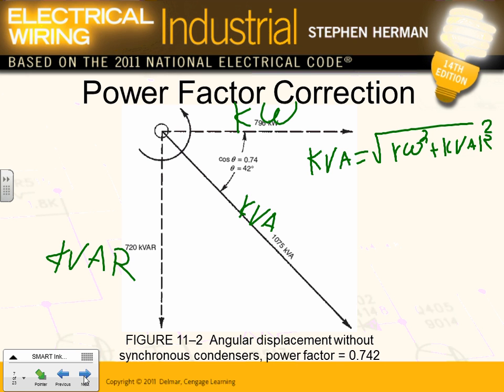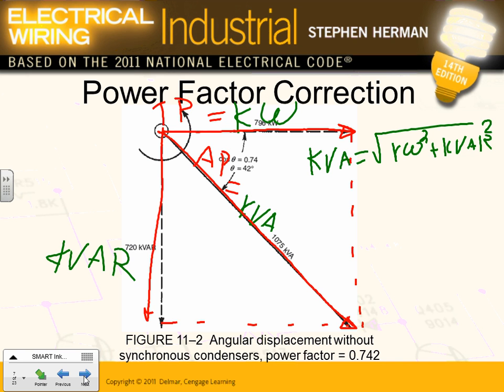So the power triangle, guys, is made out of the kW and the kvar. When you add them vectorially, this is how we add them. Here's my kW. Here's my kvar. When you add these, you end up with the apparent power right in here. You guys have seen this power triangle before, right? So what I'm going to do tomorrow is we use the power triangle to correct the power factor for a system. Any comments, guys? This piece is called the true power. This piece is called the apparent power. And this piece here is called the reactive power.